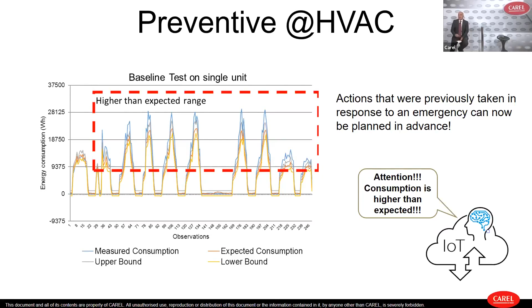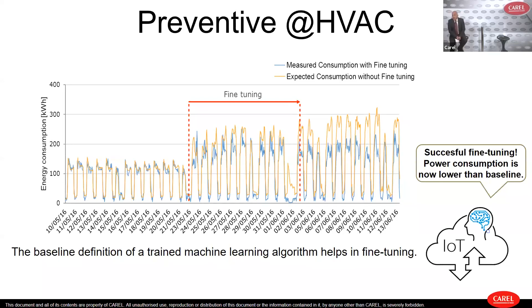And when the effective measured consumption was overcoming the threshold, the upper and lower bound created by the algorithm, the system is automatically alerting the user through a notification. And so the user can connect to the unit and perform the fine tuning, in order to also have back from the system the information that the fine tuning was successful, and the power consumption in this case, because we were considering the efficiency of the unit in terms of power consumption, is now lower than the baseline, so it came back to the reference that we created.